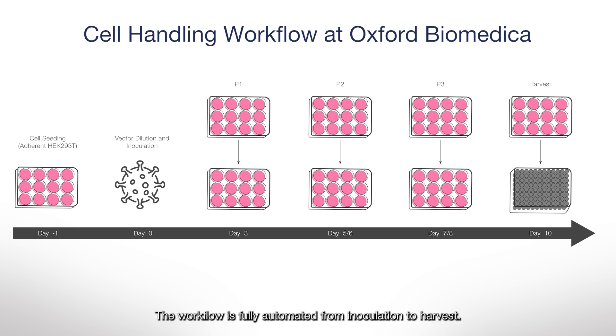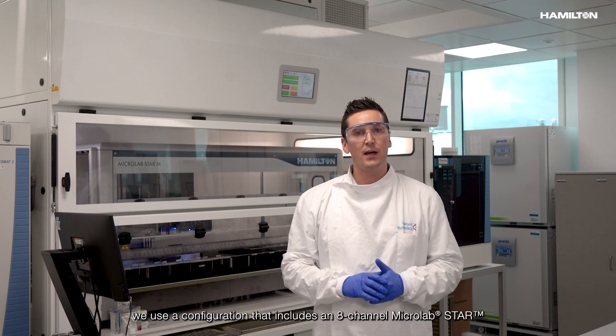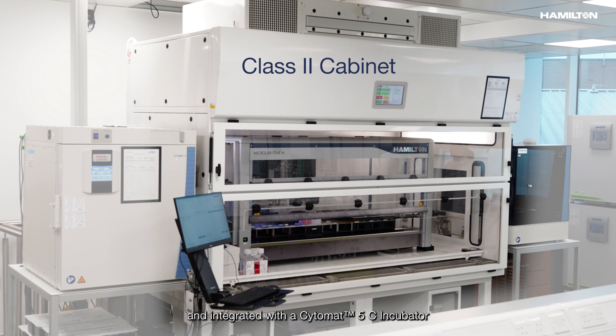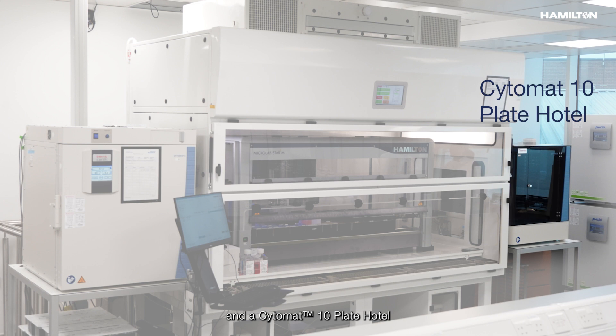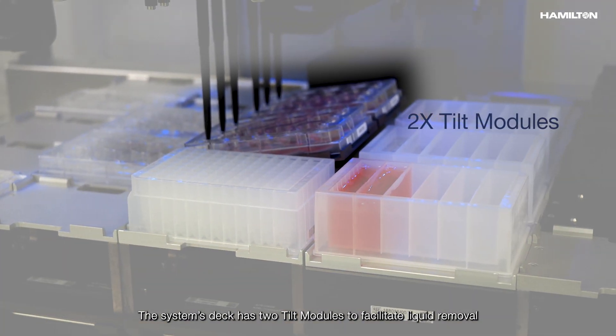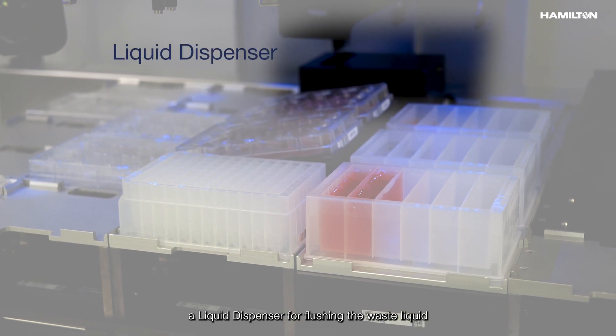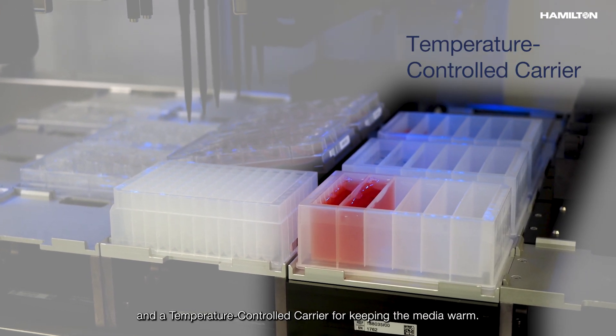The workflow is fully automated from inoculation to harvest. For these cell culture methods, we use a configuration that includes an eight-channel MicroLabSTAR enclosed in a class 2 cabinet and integrated with a Cytomat 5 C incubator and a Cytomat 10C plate hotel connected to the deck by two linear tracks. The system's deck has two tilt modules to facilitate liquid removal during cell passaging, a liquid dispenser for flushing waste liquid from the system into a waste bottle, and a temperature-controlled carrier for keeping the media warm.